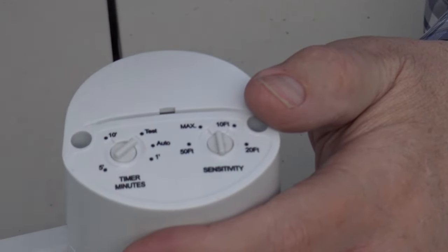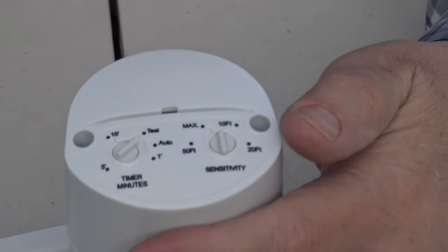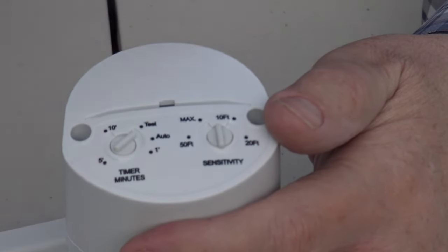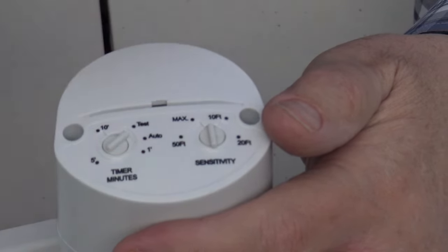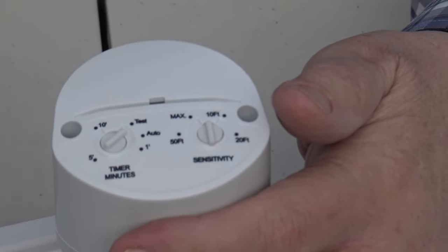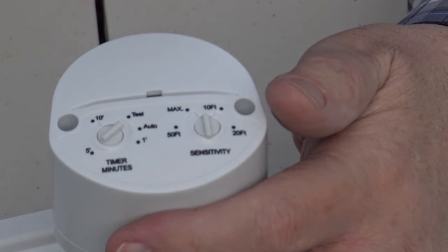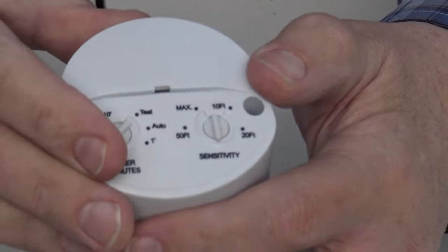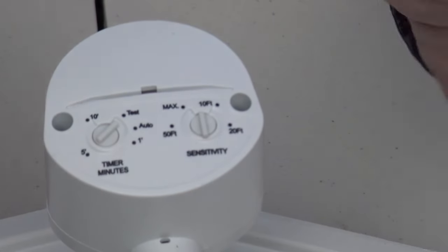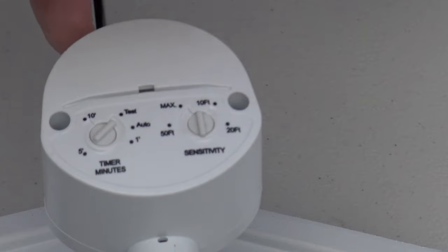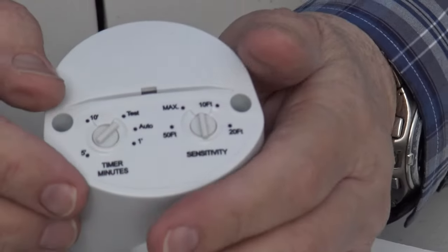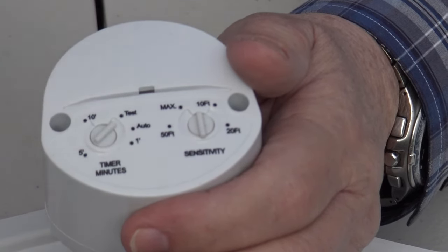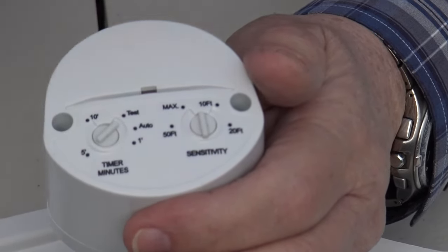And when you do that, you can actually power it on and then walk out in front of the light, walk side to side. And the reason I say side to side is that the PIR is much more sensitive in side to side motion than it is in and out. The in and out mode typically, because of the Fresnel lens, is kind of like a bicycle spokes. There's a bunch of indicators that spread out and you may be walking between indicators or sensitivity devices before it triggers. So walk side to side, that's your best bet.